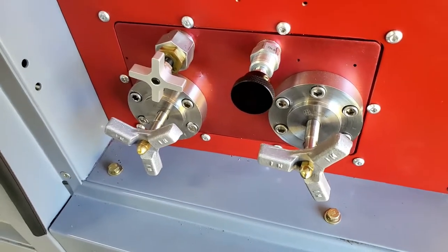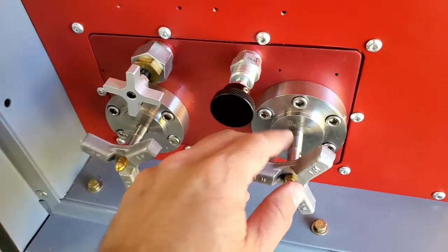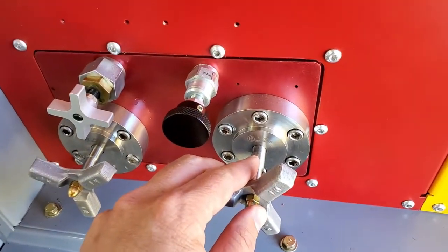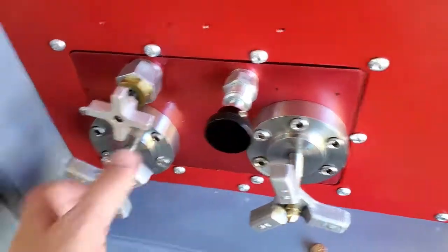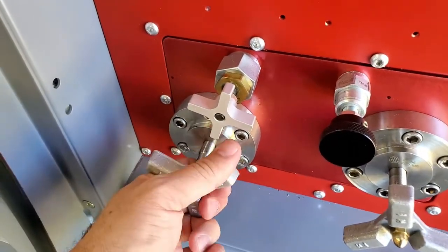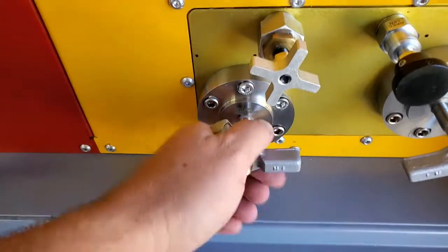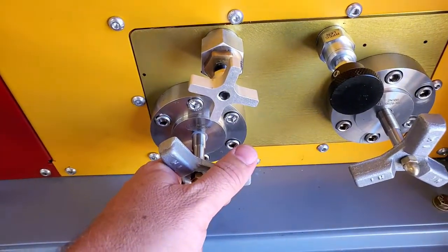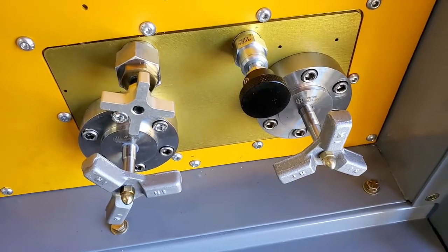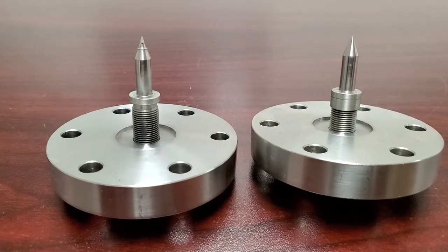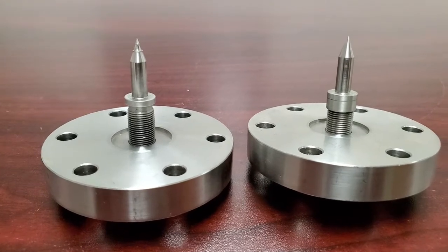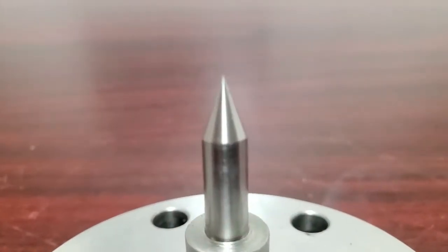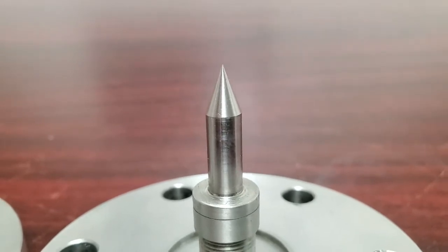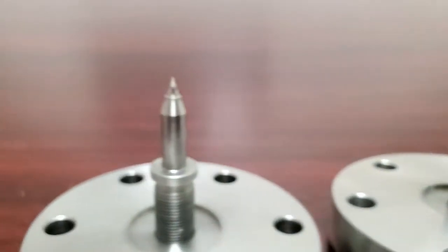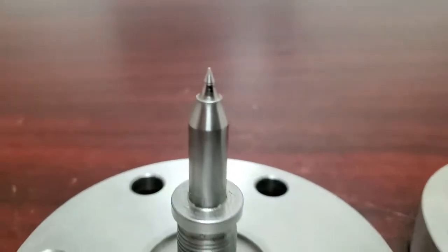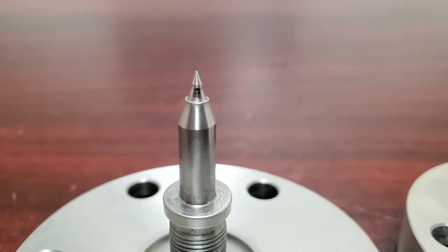Now I want to talk about your bypass valve and your supply shutoff valve real quick. At the end of the shaft is a needle point. That needle point could be damaged if you turn these in too hard. So once you've closed these, just give them a little tug. They do not have to be jam tight. If you jam them tight, you will damage them. So for point of reference, the needle on the right is in perfect condition. If you jam your supply shutoff valve or bypass valve closed too hard too many times, you will deform it and it will not seal properly.